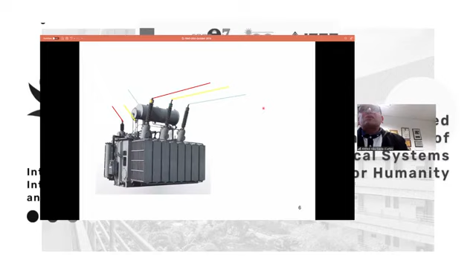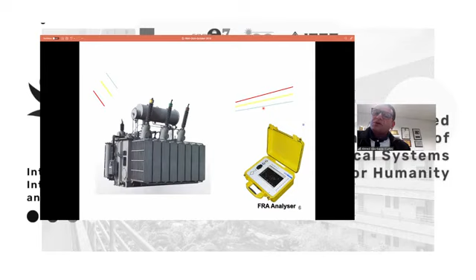So the technique, the measurement itself, is very easy and simple. Anyone can do it. But you have to take the transformer out of service because you have to scan the transformer in the right frequency range. You can't perform the test at the power frequency, 50 or 60 hertz. You need to detect inductive components, which can be detected at low frequency range, as well as capacitive components, XC equals 1 over omega C, which are detected at very high frequency. So the typical frequency range for the test would be from a very low frequency, like 10 hertz, to a very high frequency, 2 megahertz. That's why you have to take your transformer out of service, because you need to inject variable frequency into the transformer.